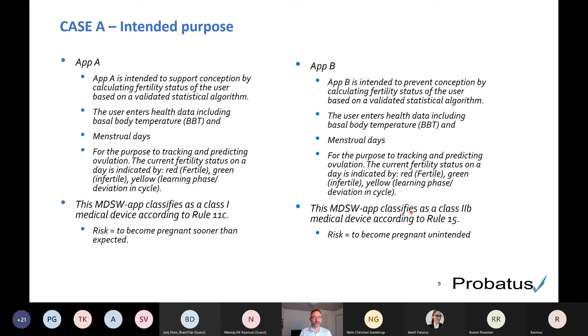And actually, if you look at the first line here, app A is intended to support conception, while the other one is intended to prevent conception. Here the risk is to become pregnant unintended, while there the risk would be that you become pregnant sooner than expected. And here you're using the app in order to become pregnant, so that would not really count as a risk, while the other one is to avoid getting pregnant, and therefore it ends up in a class 2B. So even just single words may make a huge difference in the way it is seen when we talk about intended purpose.